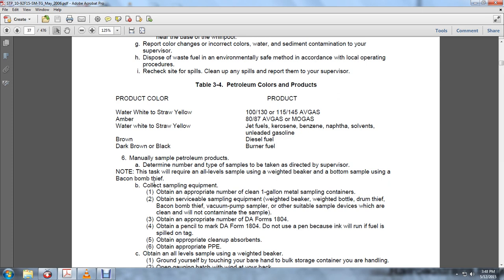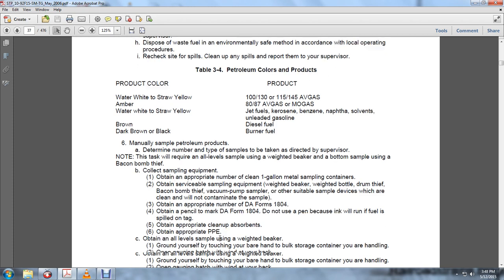Do not use ink, because ink will run in the fuel spill left on the tag. Obtain a pencil. Obtain an appropriate clean absorbent. Obtain the protective personnel equipment. Obtain all levels of sample using the weighted beaker. Ground yourself by touching the bulk storage container that you are handling with a bare hand.